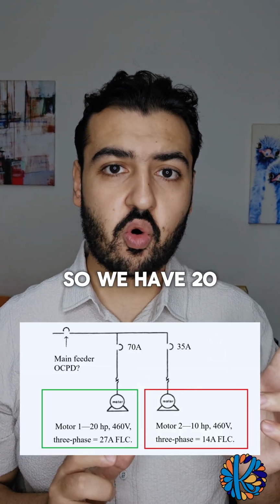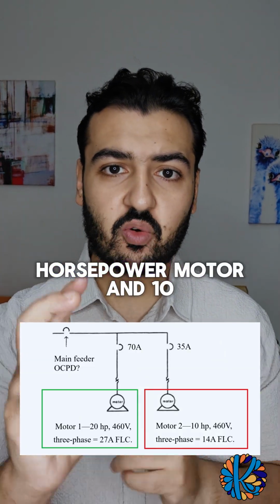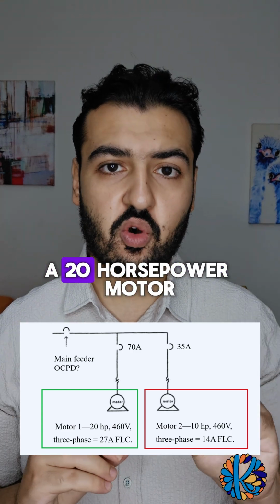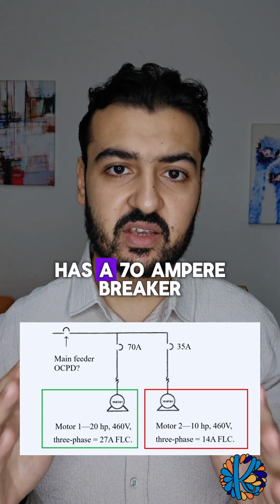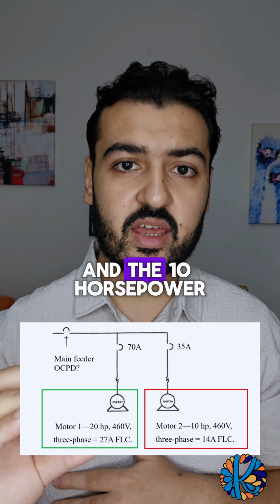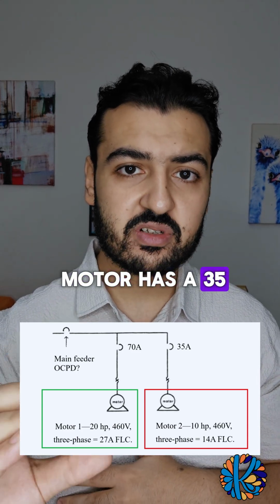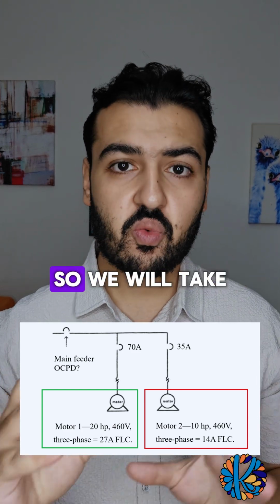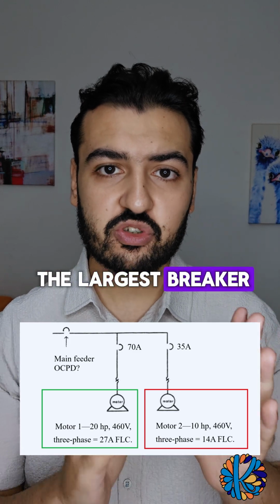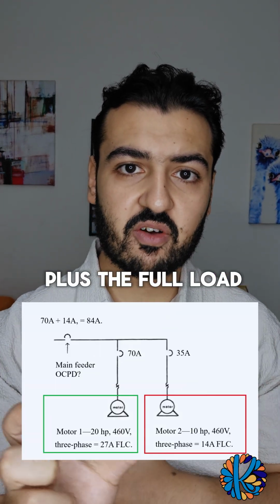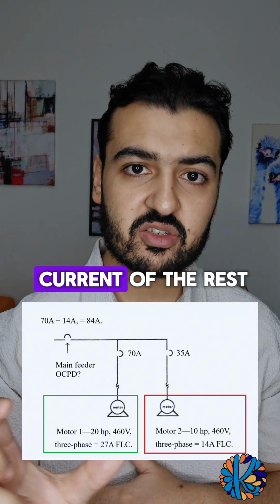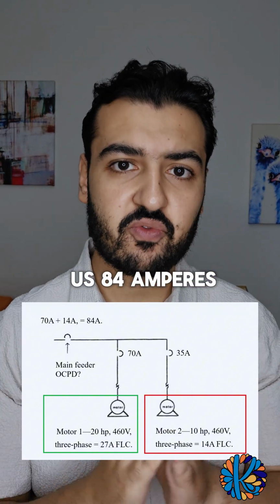So we have a 20 horsepower motor and a 10 horsepower motor. The 20 horsepower motor has a 70 ampere breaker and the 10 horsepower motor has a 35 ampere breaker. We take the largest breaker, which is 70 amperes, plus the full load current of the rest. Their summation gives us 84 amperes.